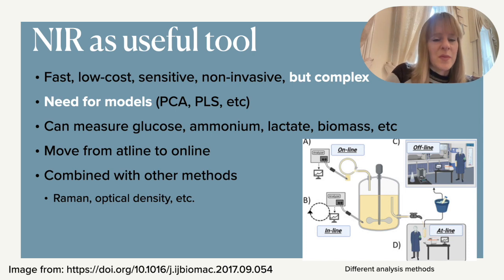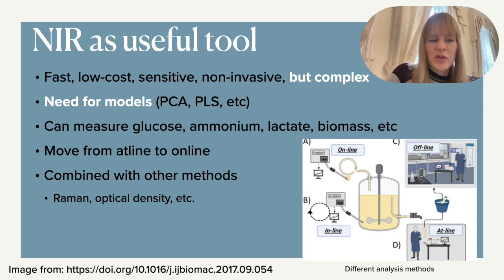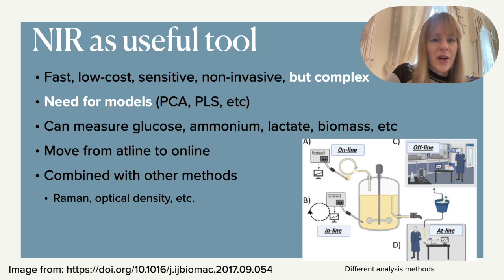The advantage of NIR is that it can measure a whole range of compounds — glucose, ammonium, lactate, many nutrients, and even biomass. NIR is particularly useful because whereas most tools used to be offline, requiring a specialist laboratory, then moved to at-line where you take a sample out of a bioreactor with a time delay of around 10–20 minutes, NIR can be used either inline or online, giving you a very fast response which is better for controlling your system.